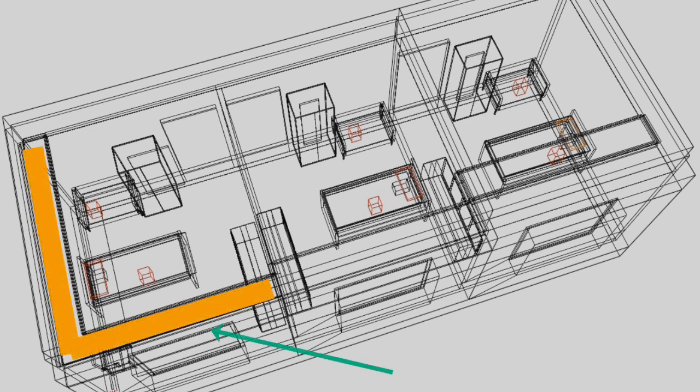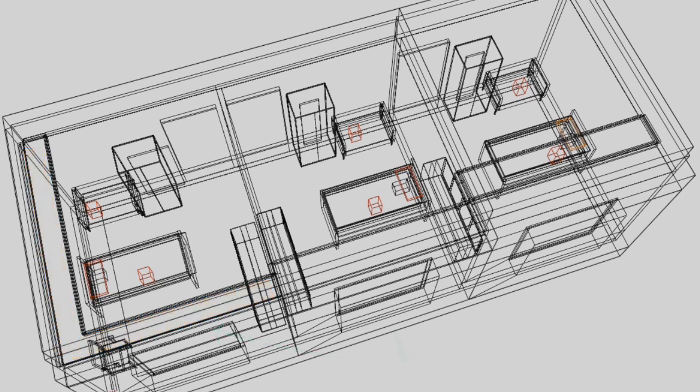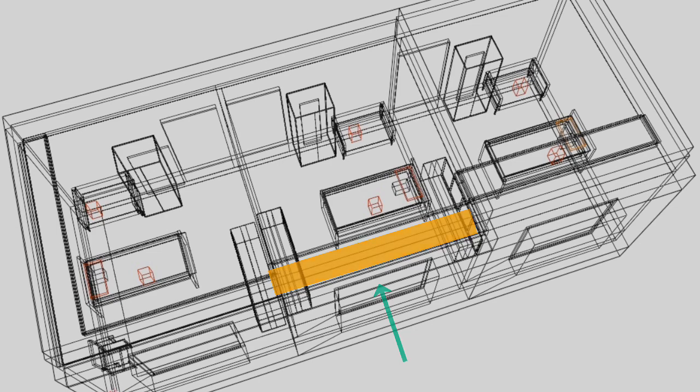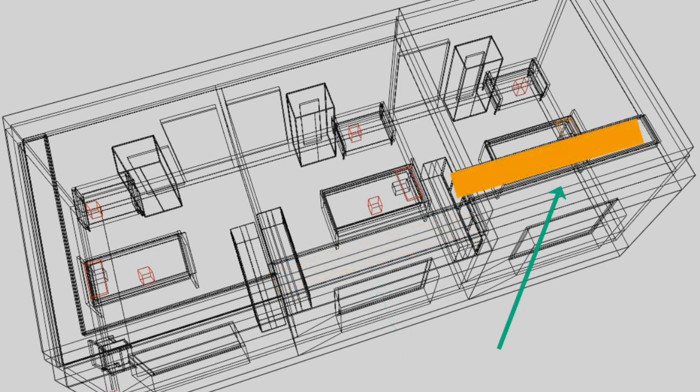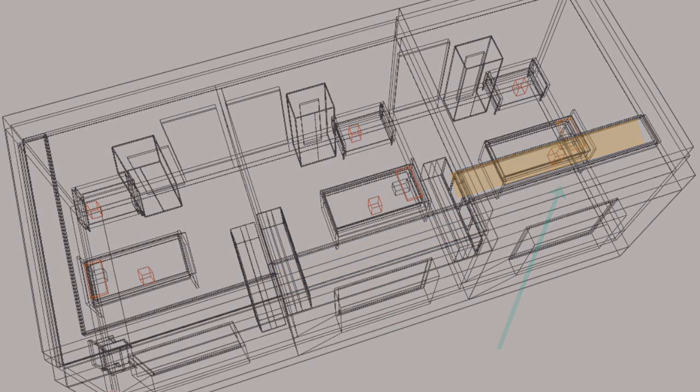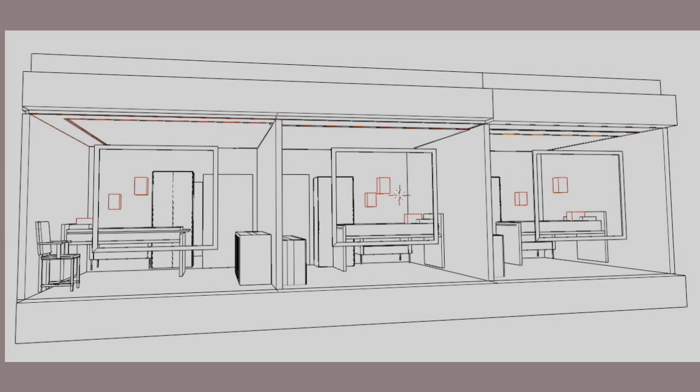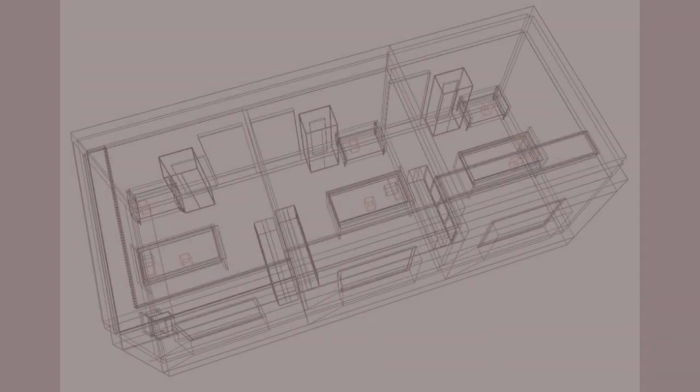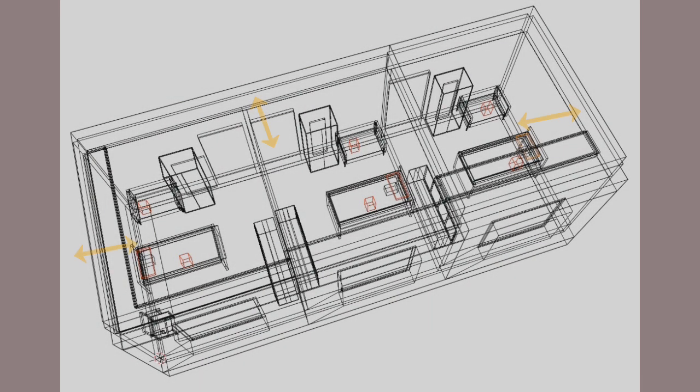Three rooms, each reflecting the proposed panel regimes. And I also included the ceiling voids above and below because ignoring boundary conditions near the heated panels is just introducing silly risk. Less of a concern is what was happening in adjacent spaces because it's a hospital. Everything's likely to be controlled fairly tightly.